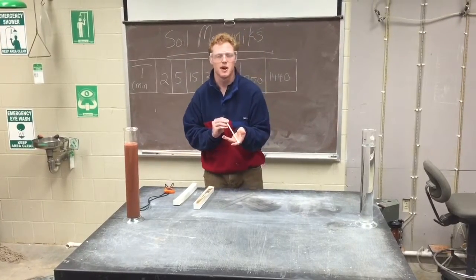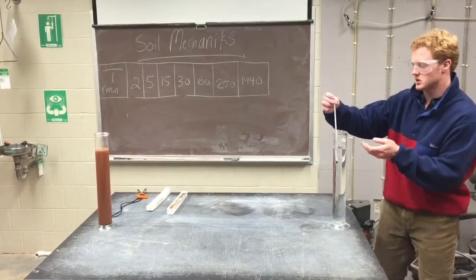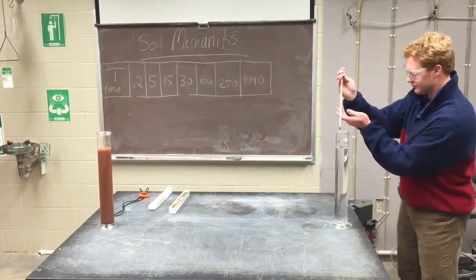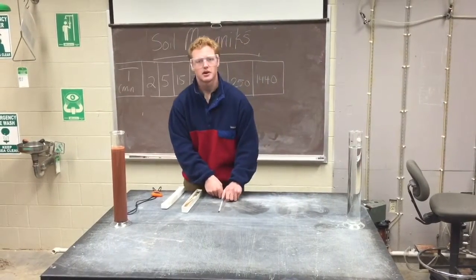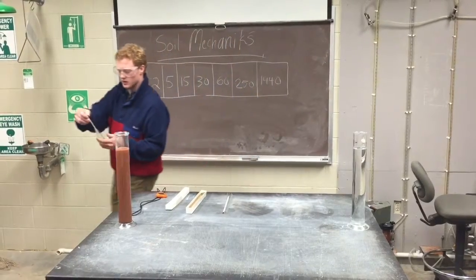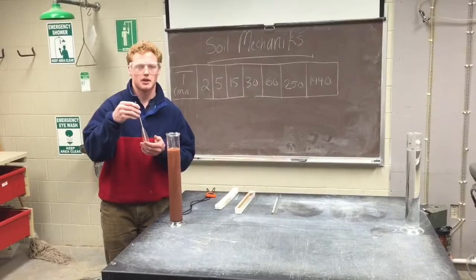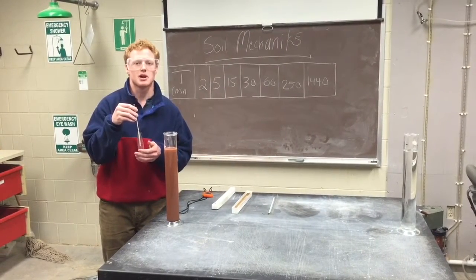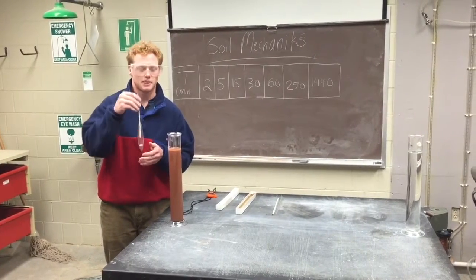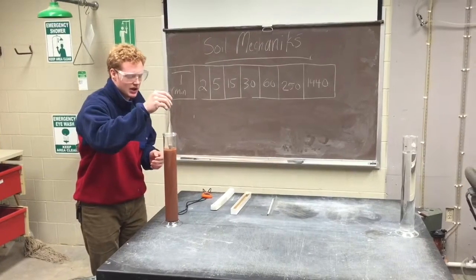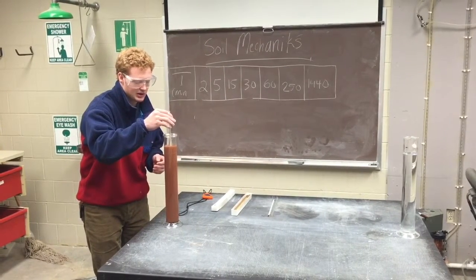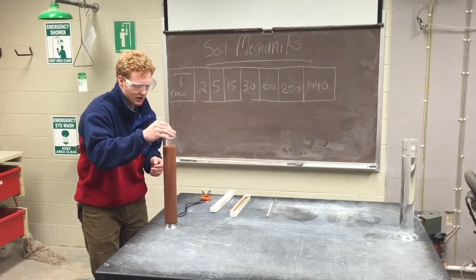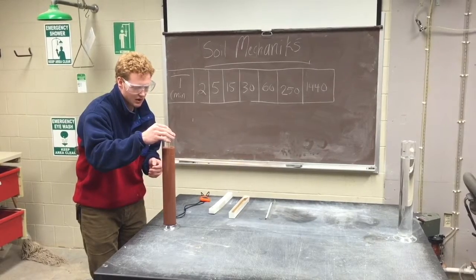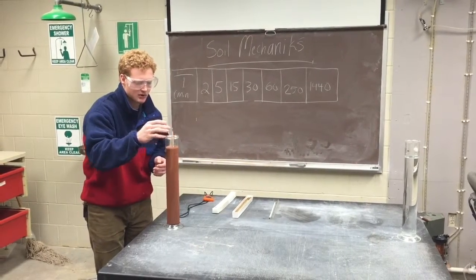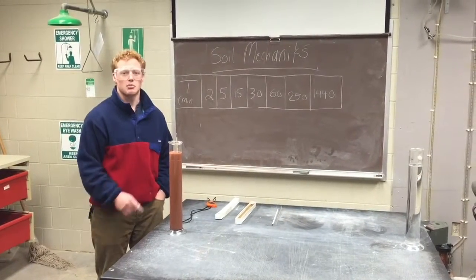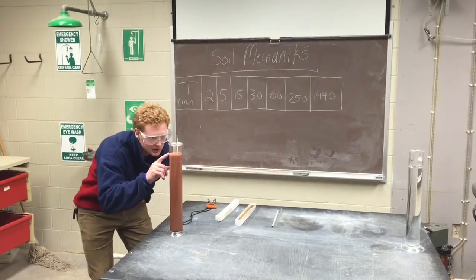This is a thermometer. A thermometer will be placed in the calibration cylinder, and readings will be taken at every time interval. 30 seconds before the 2-minute time interval commences, we want to begin to place our hydrometer into our test sample. When we place the hydrometer into the test sample, we want to be careful not to drop the hydrometer into the sample. We want to lower it slowly and carefully into the sample until it is stabilized and floating. We want to be careful to let it bob and move as little as possible. Then we will take a reading upon the hydrometer stem, reading from the top of the meniscus.